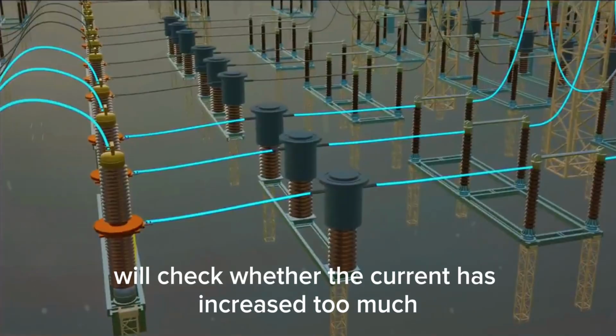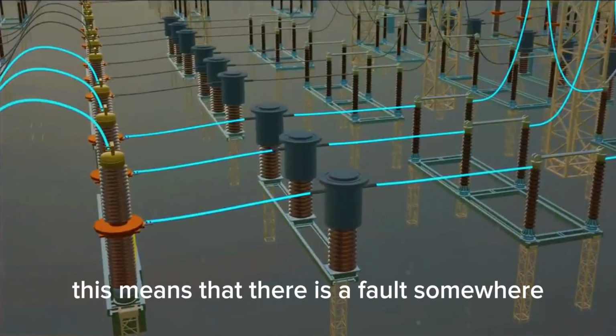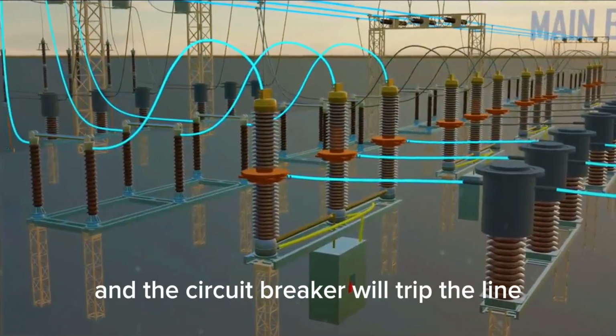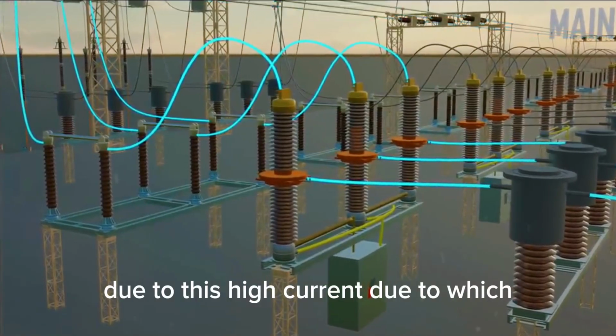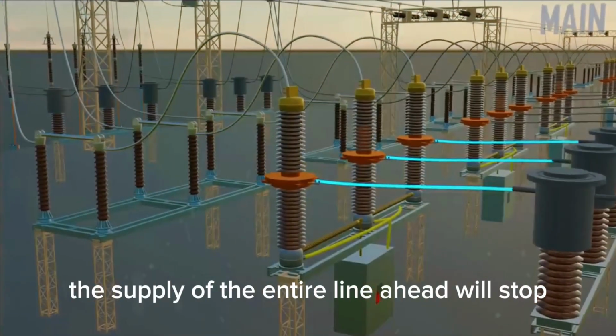So first of all, the current transformer installed here will check whether the current has increased too much. This means that there is a fault somewhere. This signal will be given to the circuit breaker, and the circuit breaker will trip the line due to this high current, due to which the supply of the entire line ahead will stop.